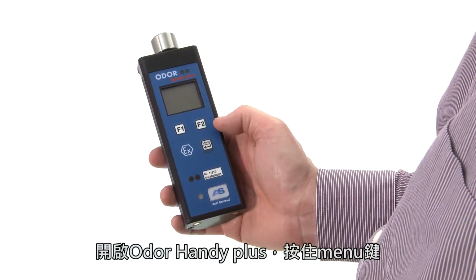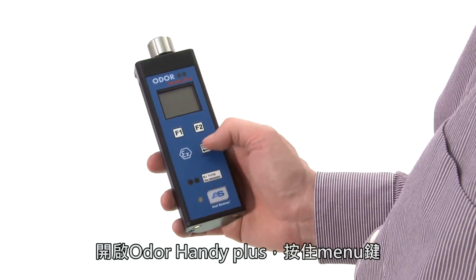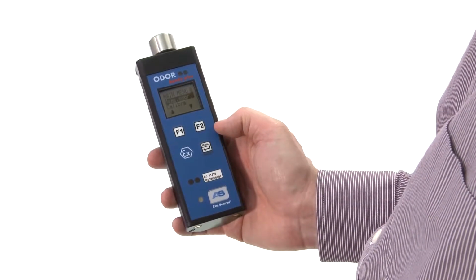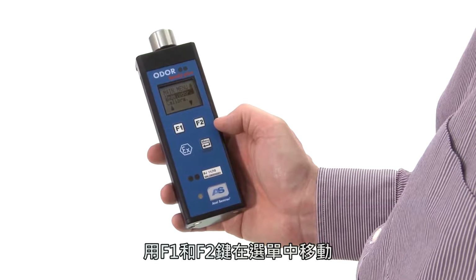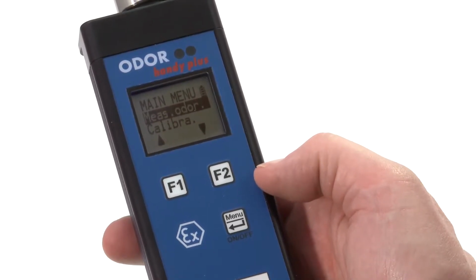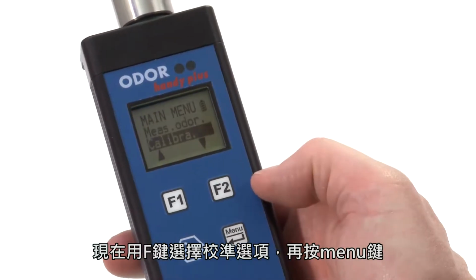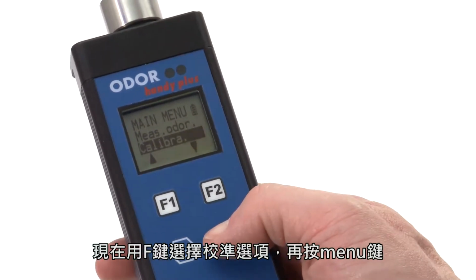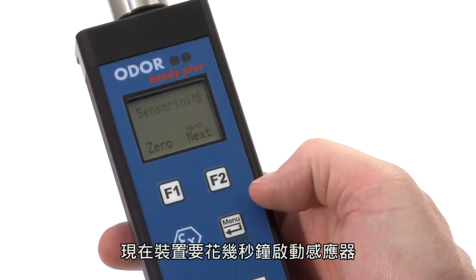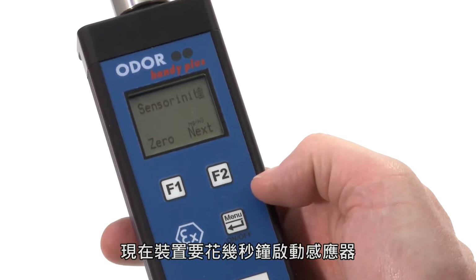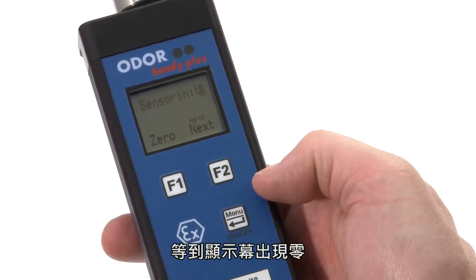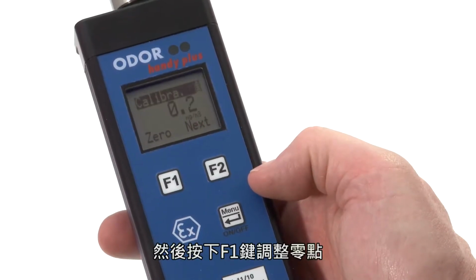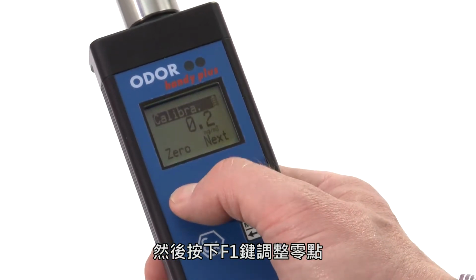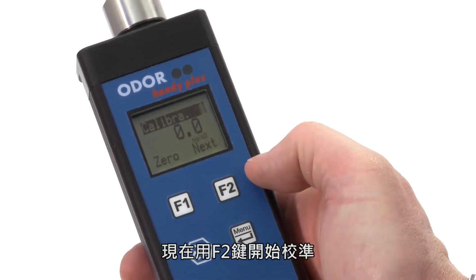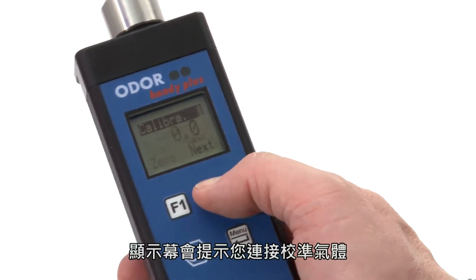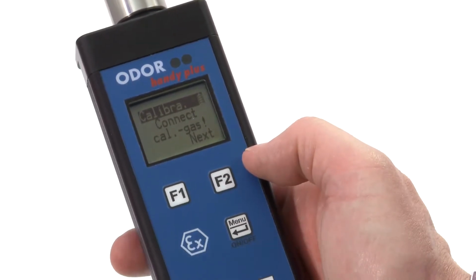Switch on the Odor Handy Plus by pressing and holding the menu button. Use the F1 and F2 keys to move in the menu. Now select the calibration menu item via the F keys and then press the menu button. The device now initializes the sensor for a few seconds. Wait for the 0 value to appear in the display. Then press the F1 key to adjust the 0 point. Now use the F2 key to start calibration. You will be prompted to connect the calibration gas.